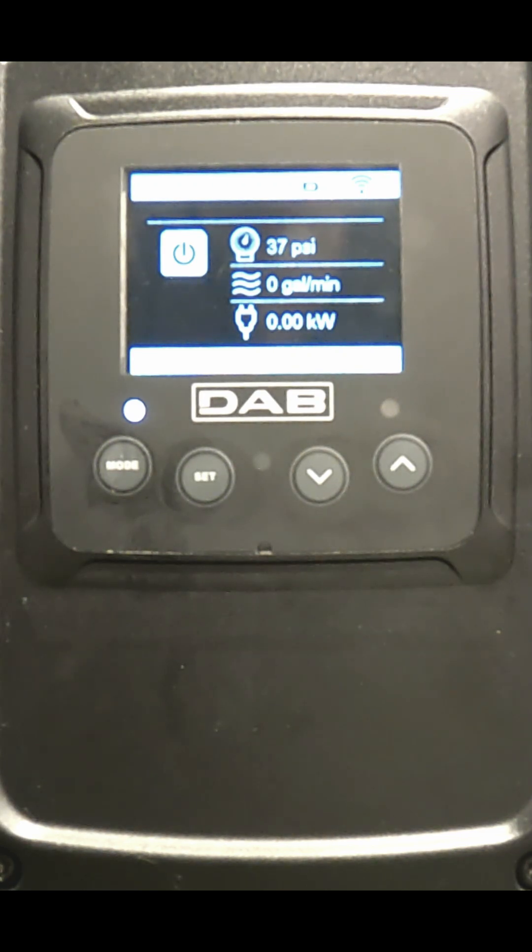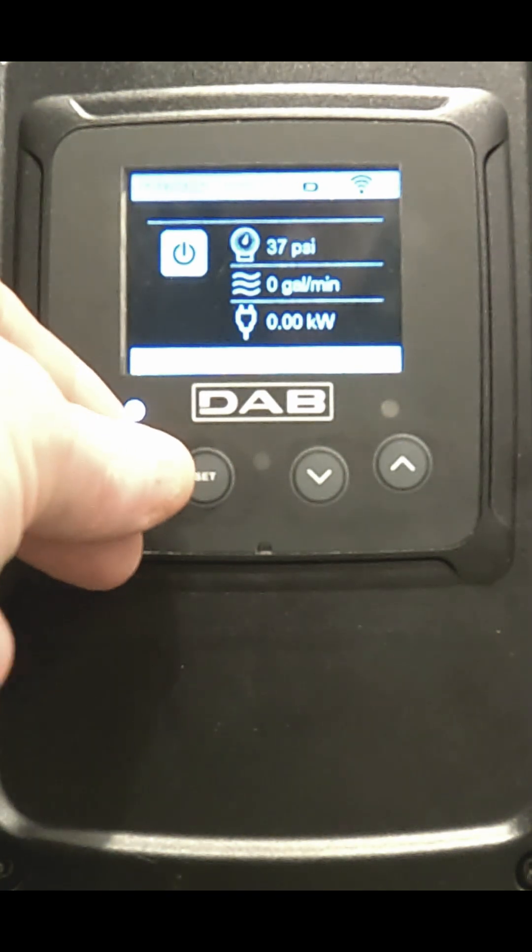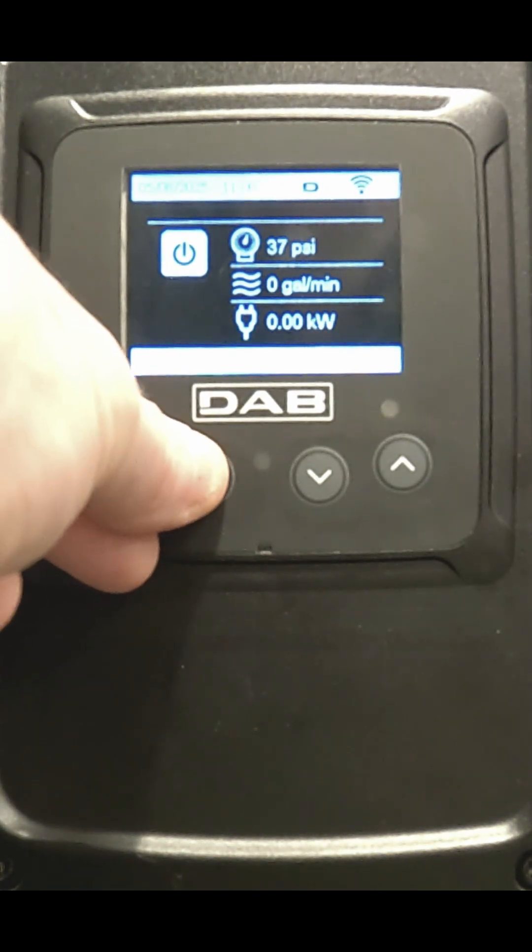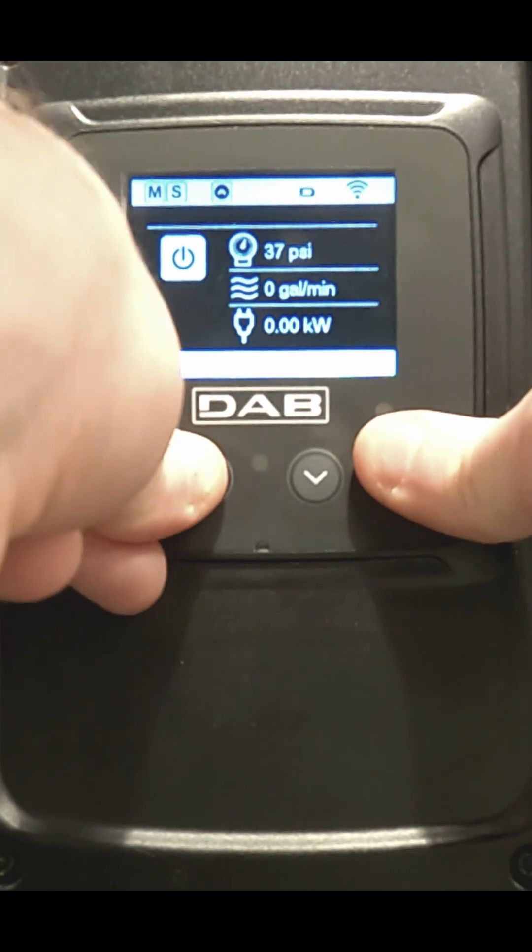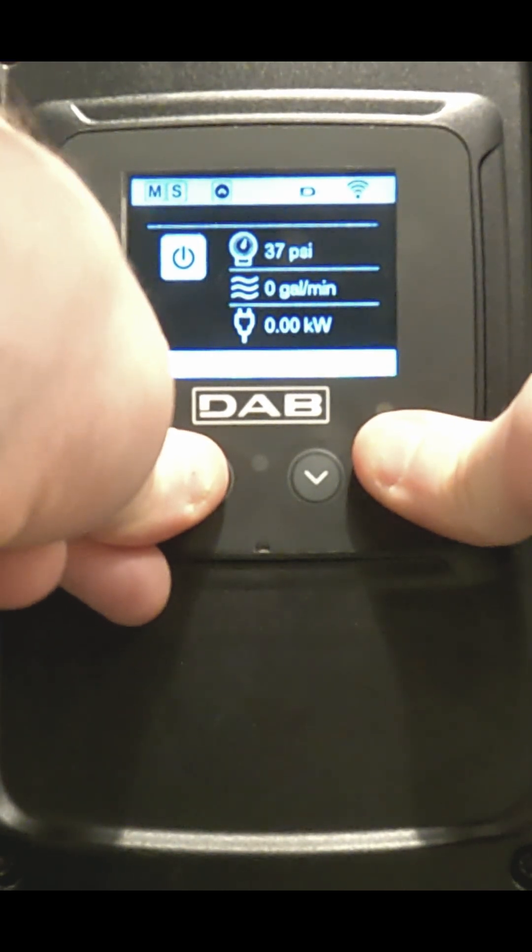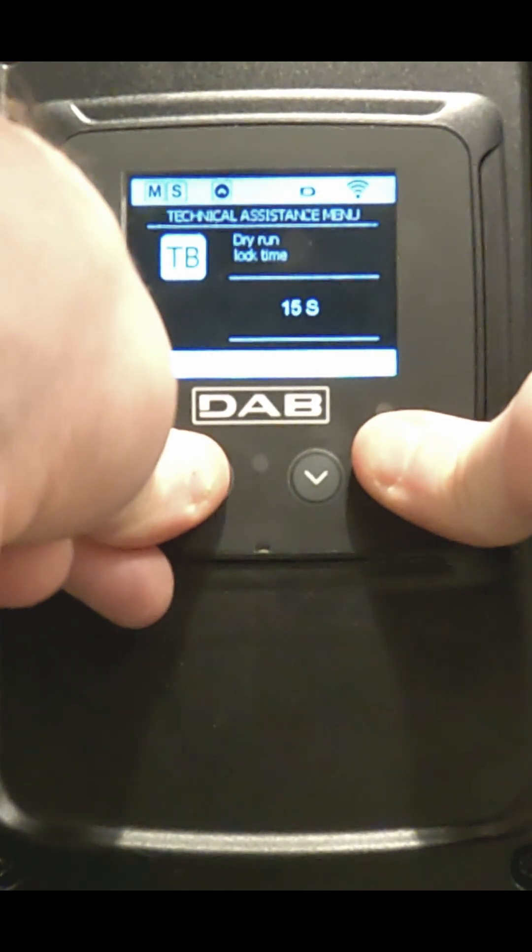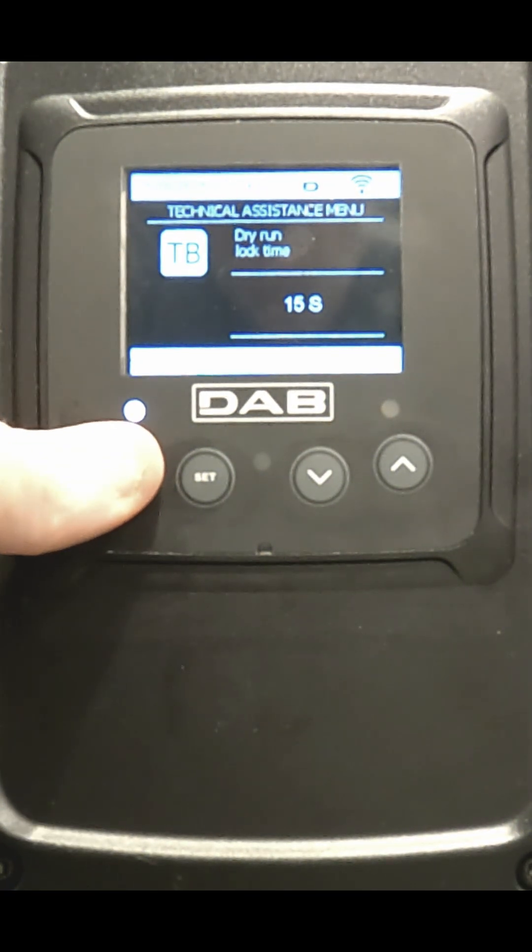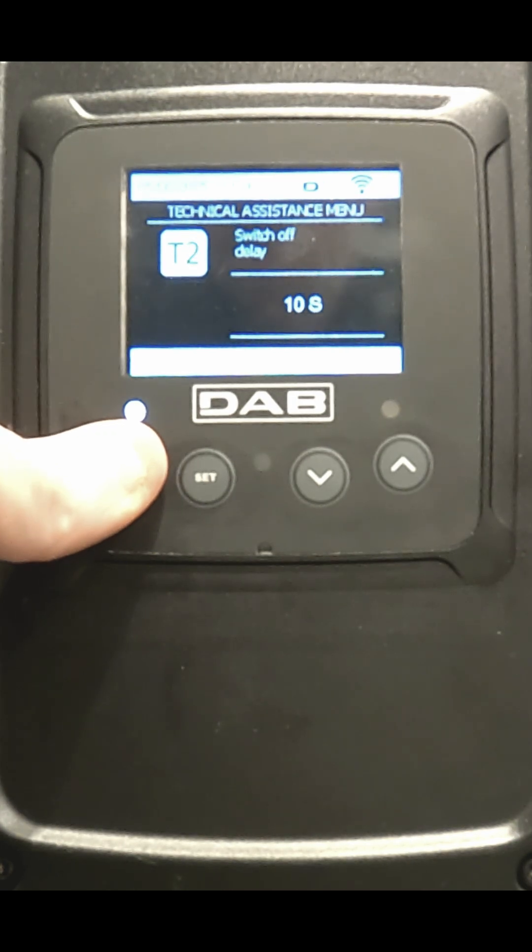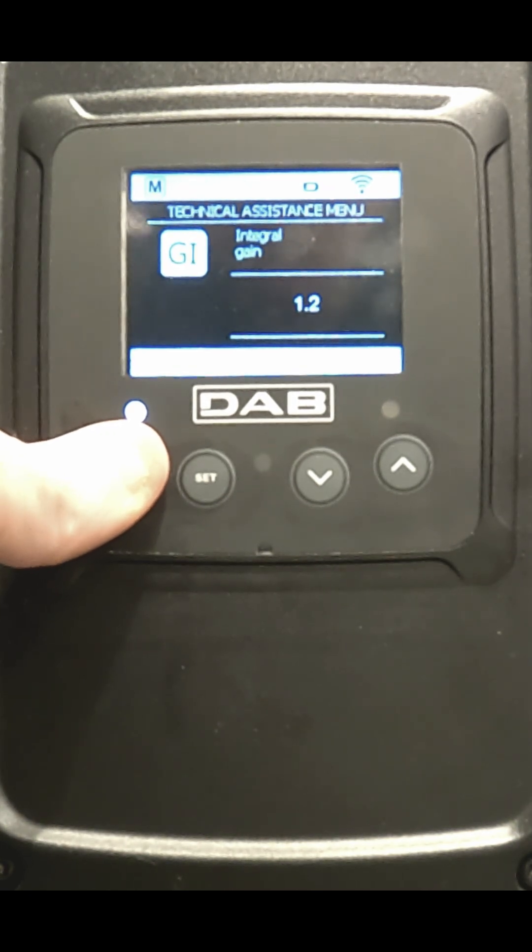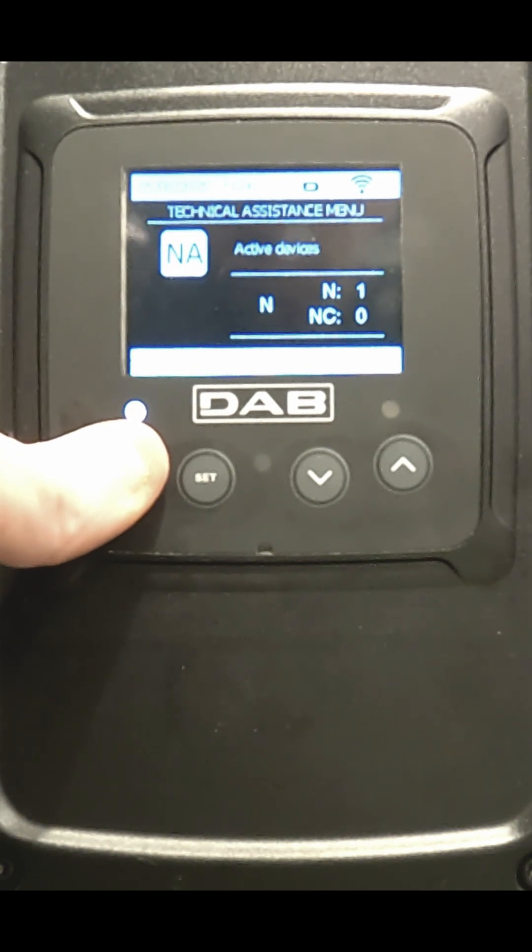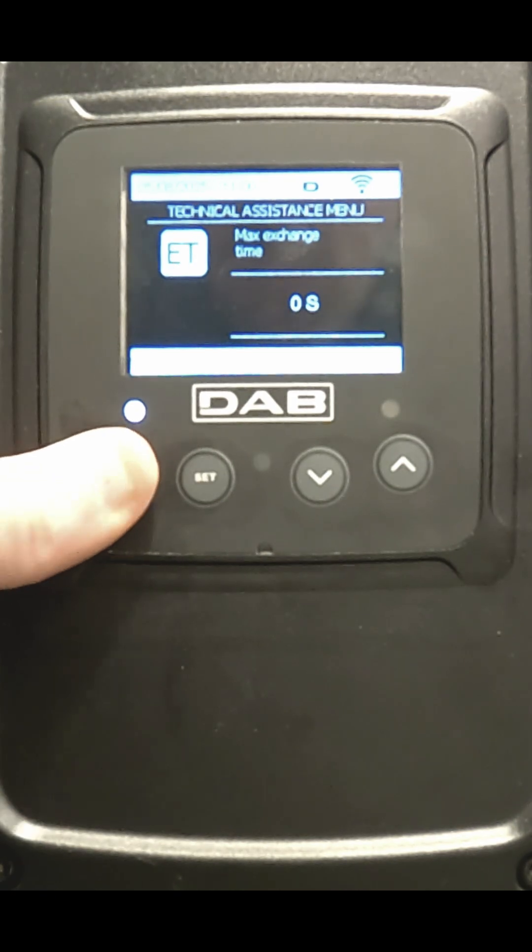You go to the technical assist menu by pressing mode, set, and the up arrow buttons for 5 seconds. Then TB will come up and you press and release the mode button until you get to the ET screen.